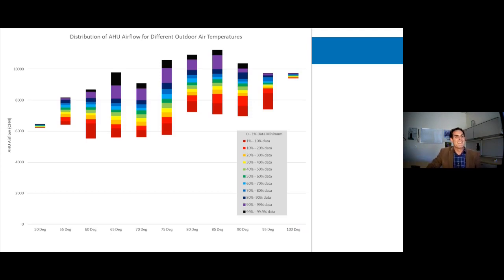the 100-degree band. And of course, I would be remiss if I didn't tell you that this air handler is a 23,000 CFM air handler. So the peak we've ever seen in it is 11,500 CFM, slightly less than half of what it's designed for.